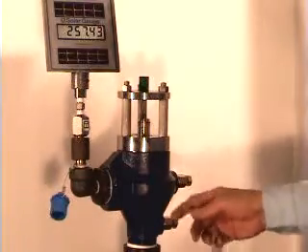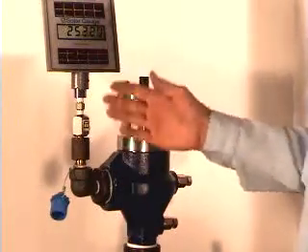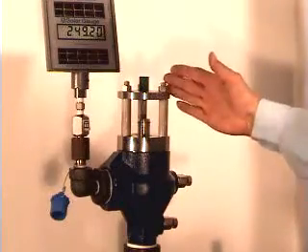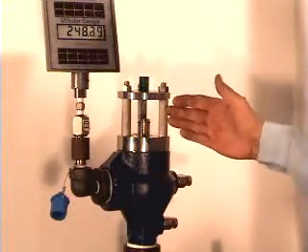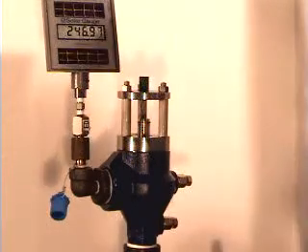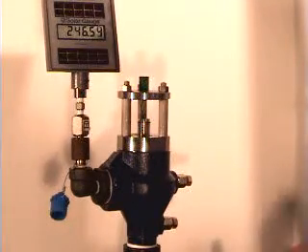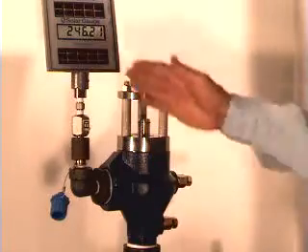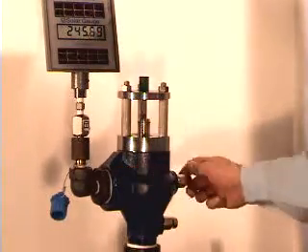You have something with excellent accuracy. You noticed that the pin buckled. It went to a closed position almost instantly. The pressure on the upstream side is increasing, but you can see there's no increase in this pressure on the top chamber.